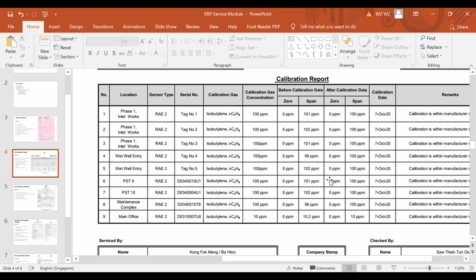Yes. So these readings are within a certain tolerance, an acceptable range. Is a range shown in this report? No, like you just indicate the readings. Because when we do calibration, we want to make sure that after calibration the reading is within a certain acceptable value, the tolerance. So is that standard shown here? It's not shown here, right? No, it's not. Would you want to show it here? I think it's fine. Okay. Maybe I clarify.